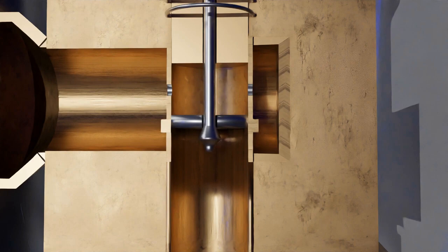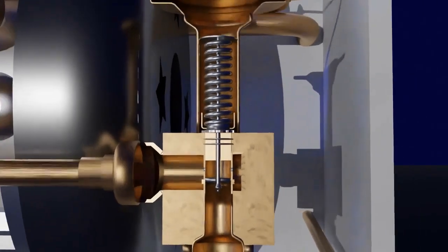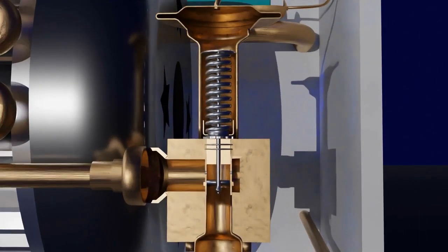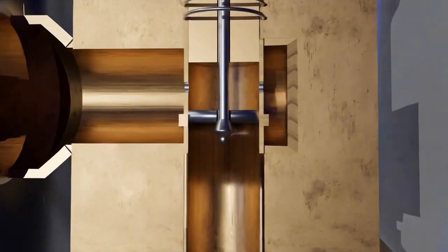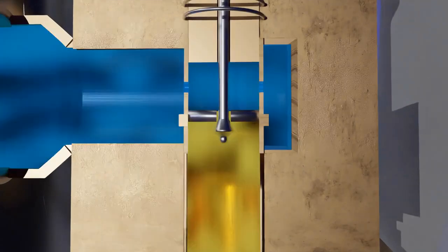When the refrigerant inside the evaporation coil is not converted completely into vapor, then it will not be superheated. The bulb will immediately sense this low temperature, and the liquid inside will contract. Then the pressure on the diaphragm will also decrease, causing the needle to move upward and narrowing the restriction. A narrow restriction causes a good amount of pressure drop, which will cause a temperature drop, thus it can absorb a good amount of heat due to its low temperature. This will make sure that all the liquid is converted into vapor.